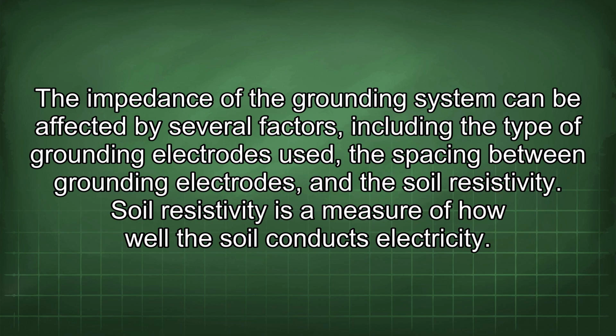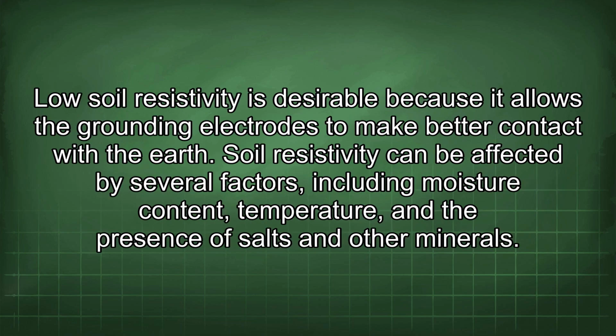Soil resistivity is a measure of how well the soil conducts electricity. Low soil resistivity is desirable because it allows the grounding electrodes to make better contact with the earth. Soil resistivity can be affected by several factors, including moisture content, temperature, and the presence of salts and other minerals.